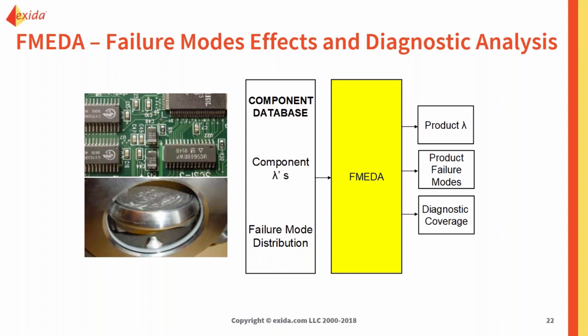It is a detailed approach of every failure mode of every component in a given design. It is a stress level for a specific design of a specific application and specific environment. So when a FMEDA is done, we get down to the manufacturer, make, series, model, that type of information, along with what type of applications it could be used for, if it's clean service, if it's severe service, if we are supposed to use it in climate controlled cabinet mounted indoor lovely facilities or if it can be thrown under the sea without any problems.